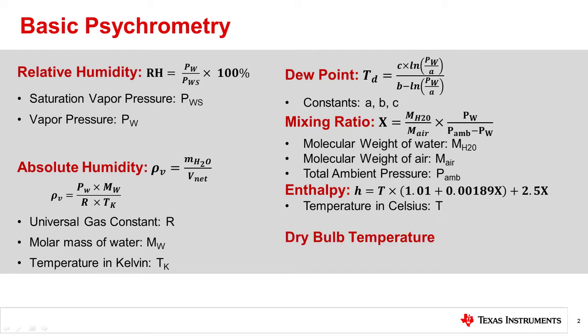Finally, we have dry bulb temperature, which is the temperature measured at a thermometer when it is shielded from radiation. This is often considered to be true ambient air temperature. Similarly, wet bulb temperature is the temperature measured at a thermometer wrapped in a wet cloth. The moisture allows evaporative cooling to occur on this thermometer, resulting in the temperature typically lower than the dry bulb temperature. We will cover these two quantities a little bit more when we discuss psychrometers.